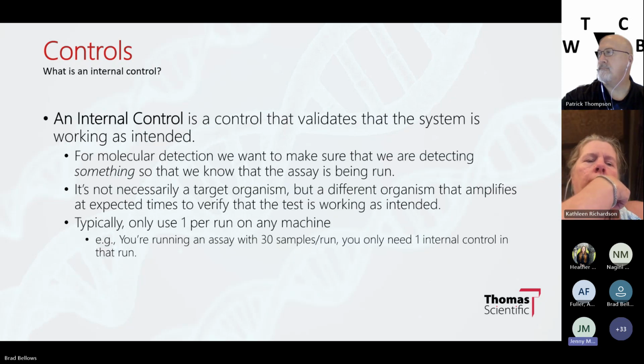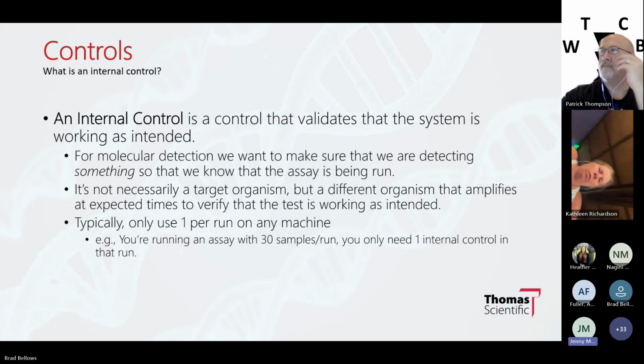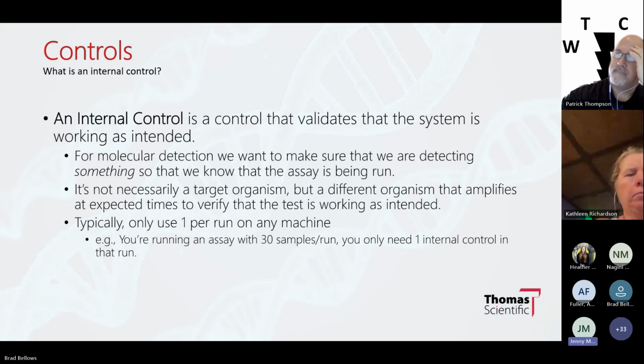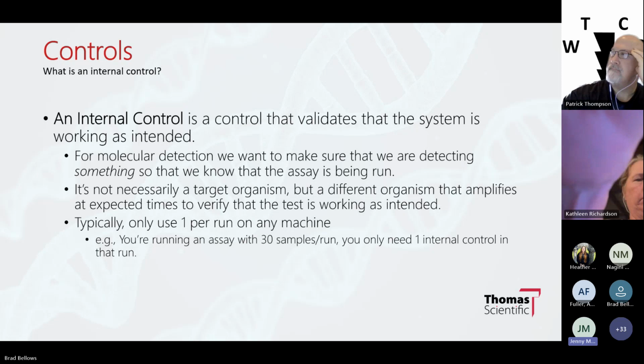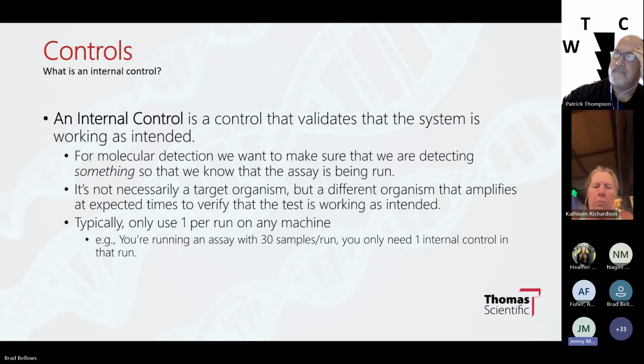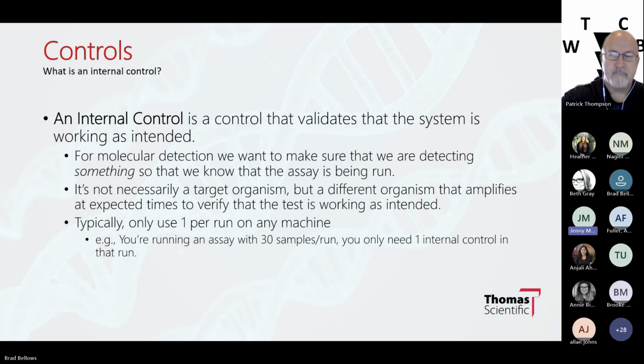So what's an internal control? An internal control is a control that validates that the system is working as intended. Specifically for molecular detection, we want to make sure that we're detecting something so that we know that the technology is actually going to do what we expect it to do, which is amplify either DNA or RNA. It's not necessarily the targeted organism or sample, but it may be a different organism that amplifies at expected times to verify that that test is working as intended.